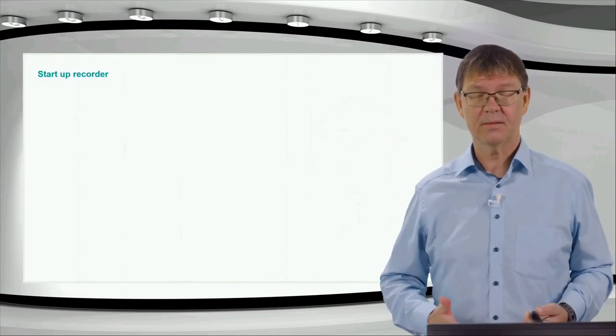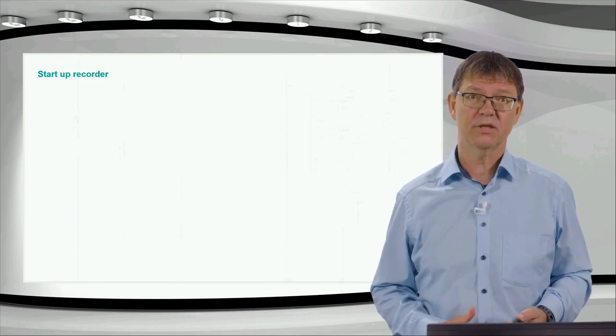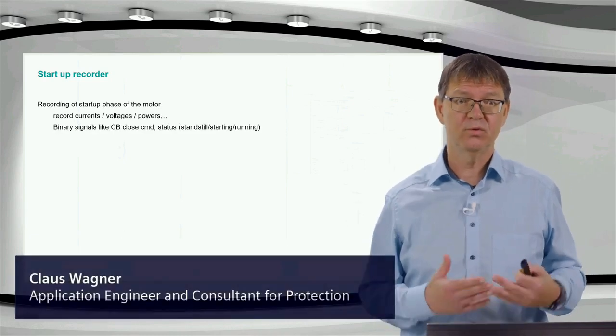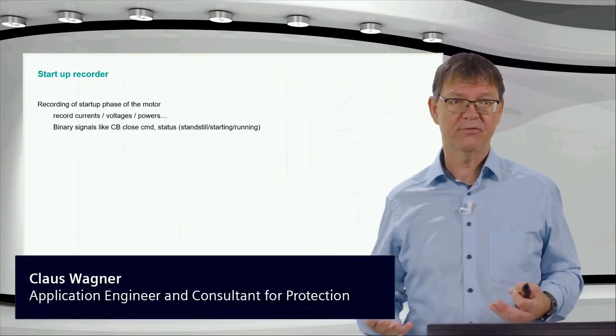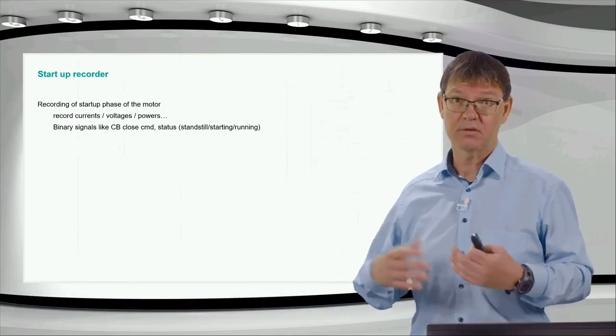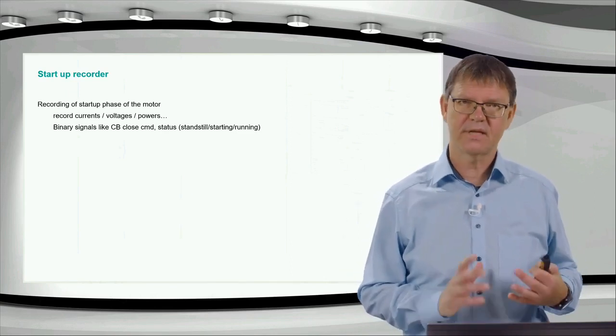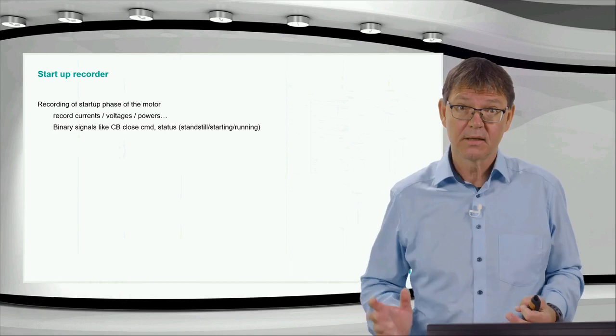Let's start with a startup recorder. It's a built-in function now in the motor protection. And what do we do? We record the startup phase of the motors. What can we record? Currents, voltages, power, binary signals like the circuit breaker close commands, the status of the motor, and so on.